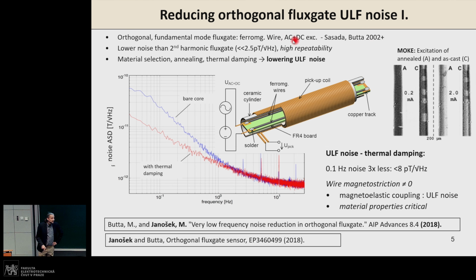And the biggest difference between the second harmonic fluxgate and the fundamental mode orthogonal fluxgate we are using is that we can lower the noise because of a different principle of operation. So instead of exciting the sensor to saturation and back, we are using here quite a high DC component with an AC component of excitation, which goes through the ferromagnetic wires. And because we don't have any, or in the best case, we don't have any domain wall movements or reversals, we are only rotating the magnetization, so we can get rid of most of the noise.